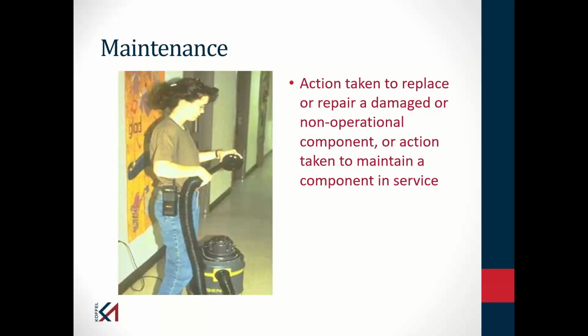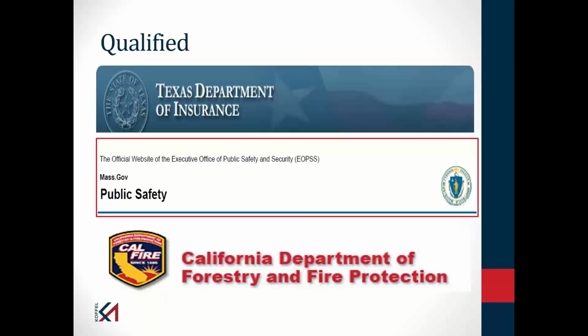Here we see somebody cleaning a smoke detector. Manufacturers will typically give us maintenance of the device, how it should be performed. NFPA 25 may give us maintenance activities, may tell us to do it in accordance with the manufacturer's instructions, but I'm doing some action to repair a damaged component or putting the component back in service. And again, now I need to know more than just generic information about the device. I need to know exactly what's required.